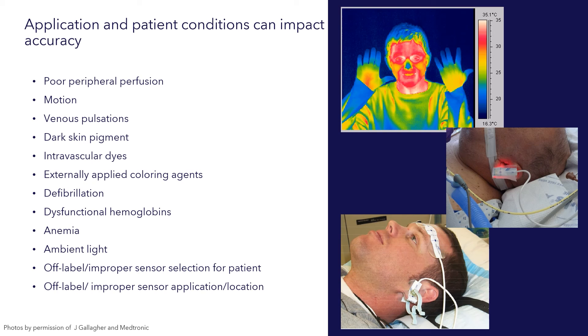Two of the last things that we want to talk about are off-label or improper sensor selection or use on the patient in the improper location. In the last picture, we see a finger probe placed on the patient's forehead. This is a transmission sensor being used as a reflectance sensor and can provide inaccuracies. Often when the sensor is used in this way, it will show an artificially high oxygen saturation reading, which may become problematic as the patient desaturates but the measured saturation with this probe does not reflect that change in saturation.